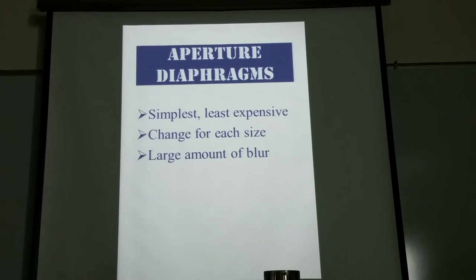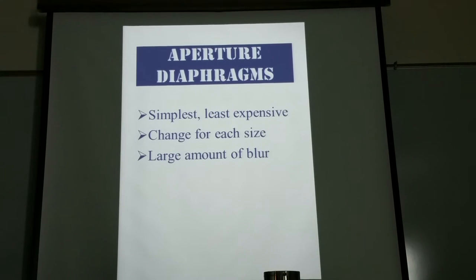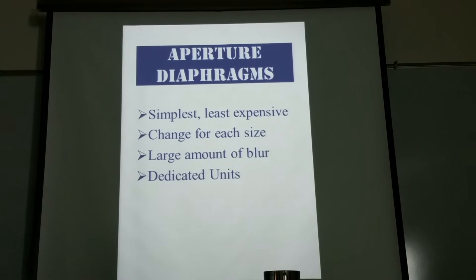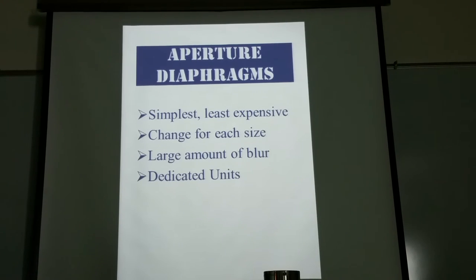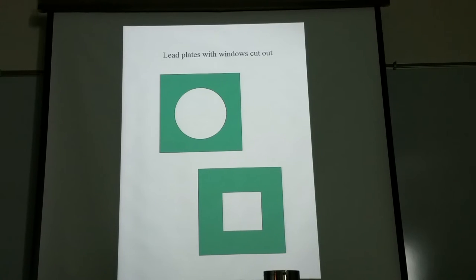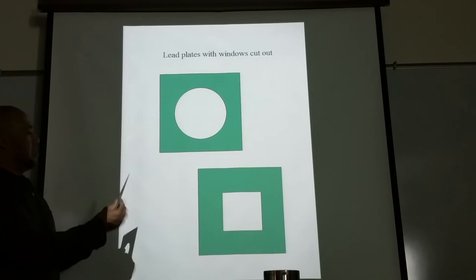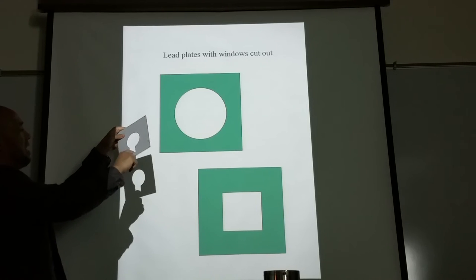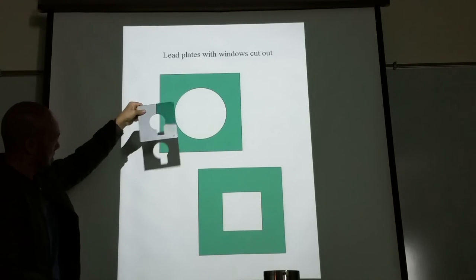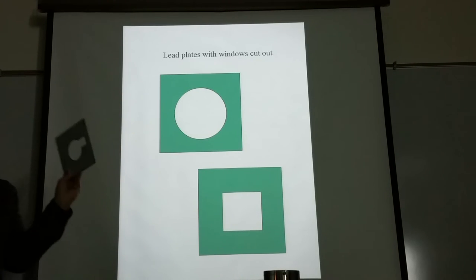Another problem with the aperture diaphragm is that there remains a large amount of blur on the edges of the beam. Although it controls beam size, it doesn't clean out the edges, which produces penumbra or blur on the radiographic image. Aperture diaphragms are the simplest and least expensive option, but they are constructed for dedicated units only, made for specific special units.